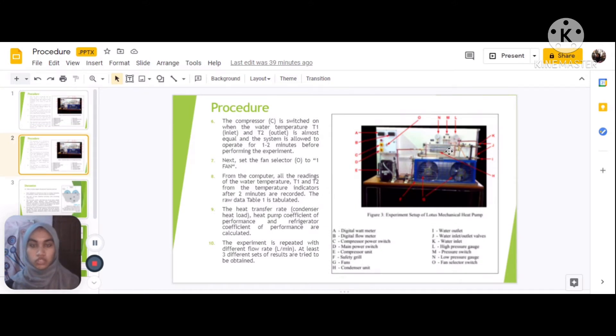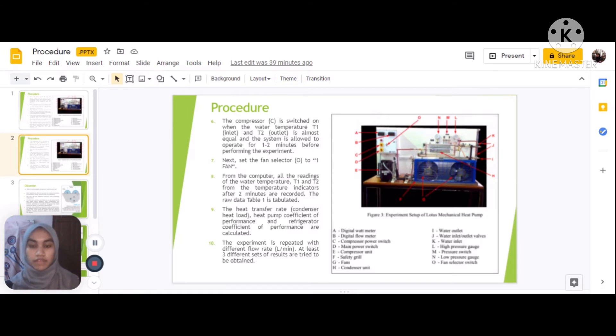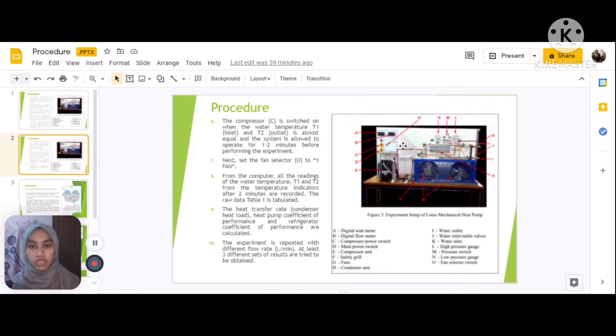Sixth, the compressor C is switched on when the water temperature T1 inlet and T2 outlet are almost equal, and the system is allowed to operate for 1 to 2 minutes before performing the experiment. Next, set the fan selector O at 1 fan. Then record all readings of water temperature T1 and T2 from the temperature indicators after 2 minutes.